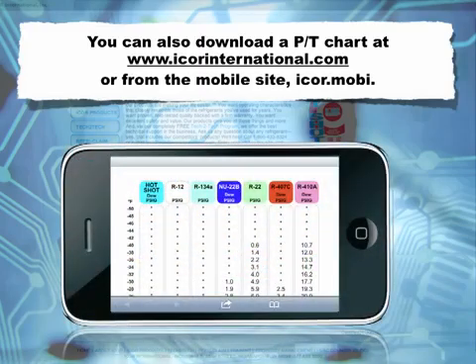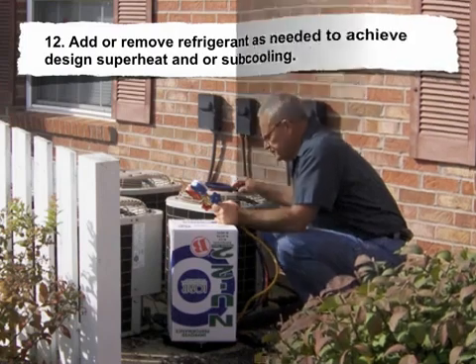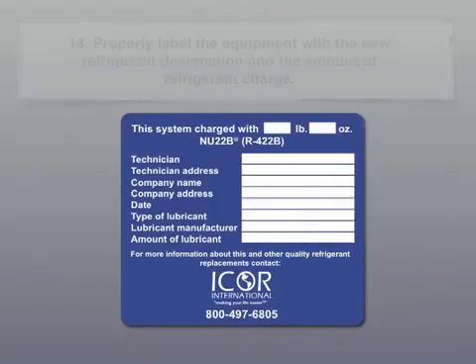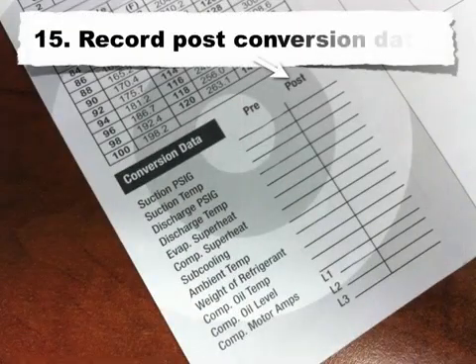You can download a PT chart at www.icorinternational.com or from the mobile site, icor.mobi. Step 12: Add or remove refrigerant as needed to achieve design superheat and/or subcooling. Step 13: Check the pressure safety controls and condenser fan cycling control for proper setting. Step 14: Properly label the equipment with the new refrigerant designation and the amount of refrigerant charge. Step 15: Record post-conversion data.